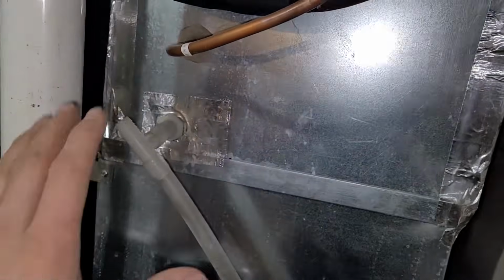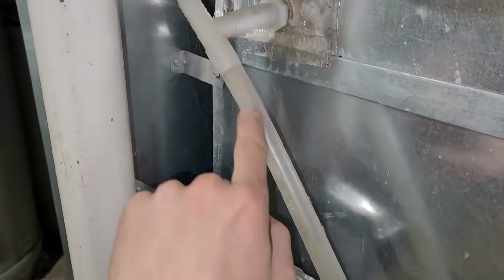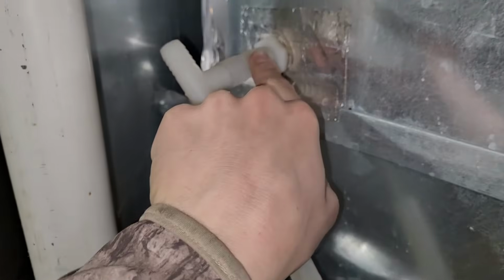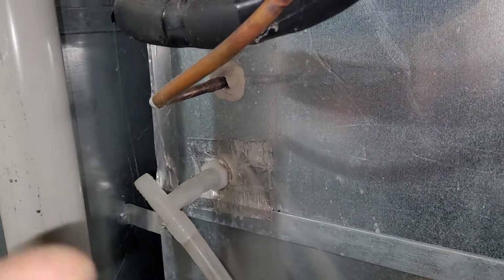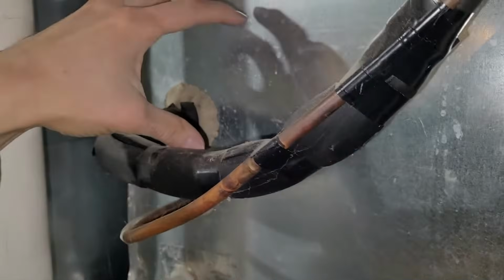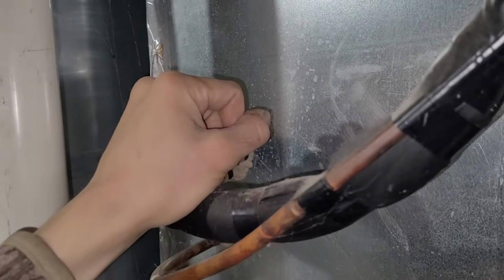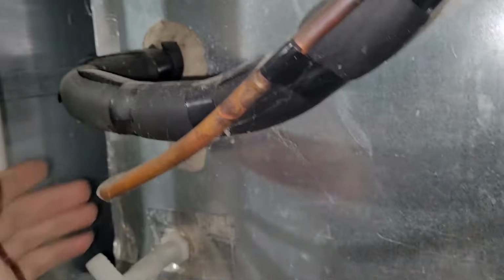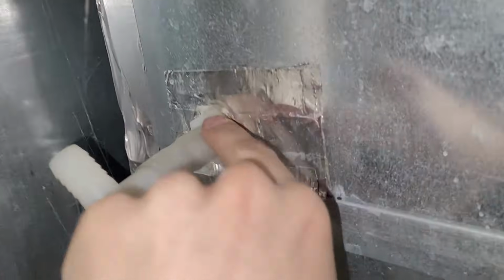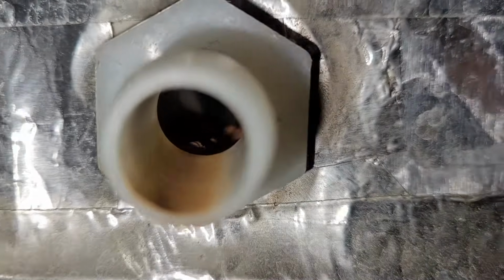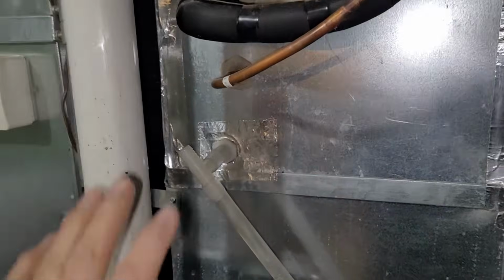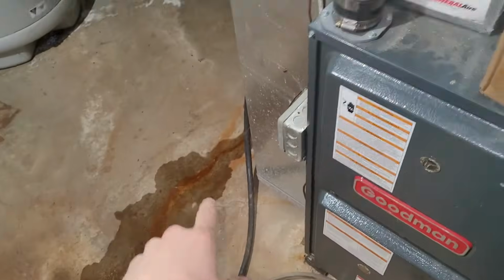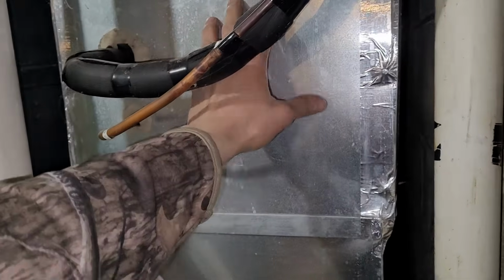Second common cause is the air conditioner. If the air conditioner gets plugged here or here and the system is running, that coil gets really cold, moisture condenses onto the coil, and that runs down and drains into a pan here. So if it gets plugged in this little nipple right here, that can be a really common cause. You can see there's a little bit of debris in there, but not much. If it's summer and you've got water running out, most likely it's related to the air conditioner coil.